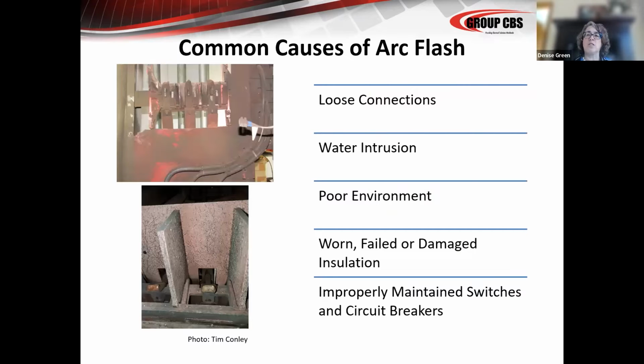Common causes of arc flash that are related to maintenance. Loose connections, obviously. Water intrusion. Water intrusion cannot just be an active leak. It might be an environmental situation where there's condensation, there's water in a trough below a substation that's evaporating continually onto the gear. So water intrusion takes several different facets when combined with electricity. So it's important to remember that not just an active leak can cause an issue.